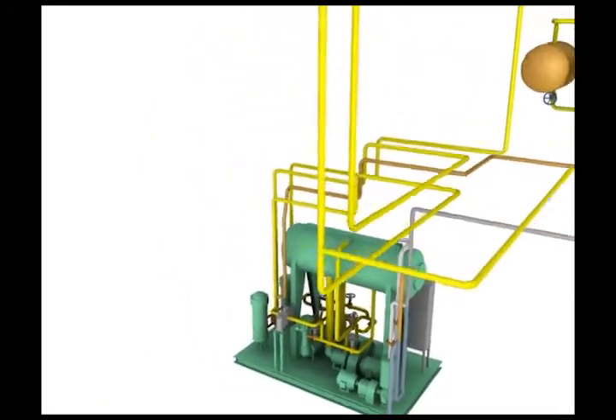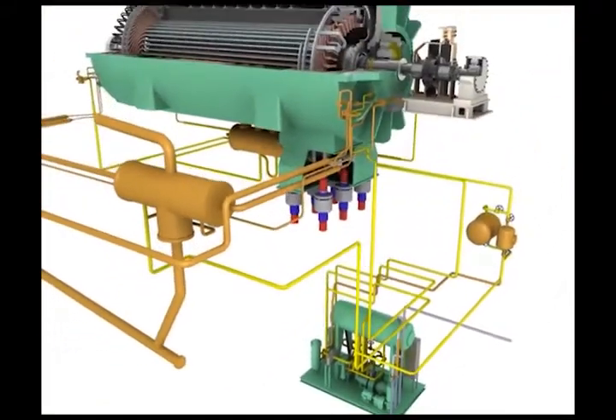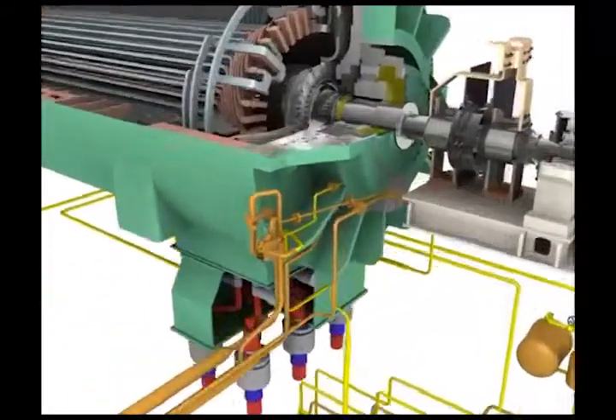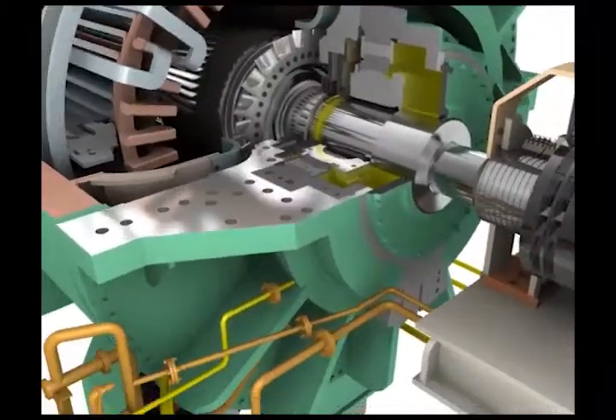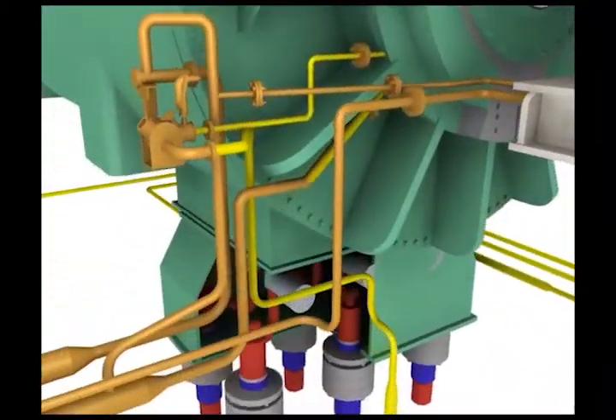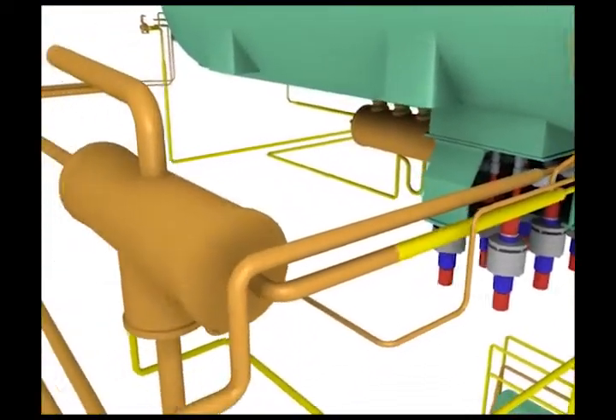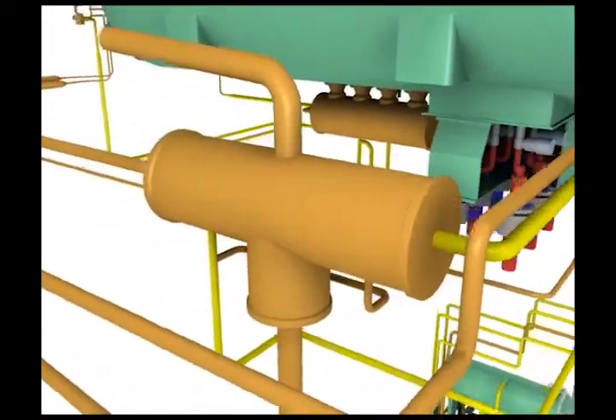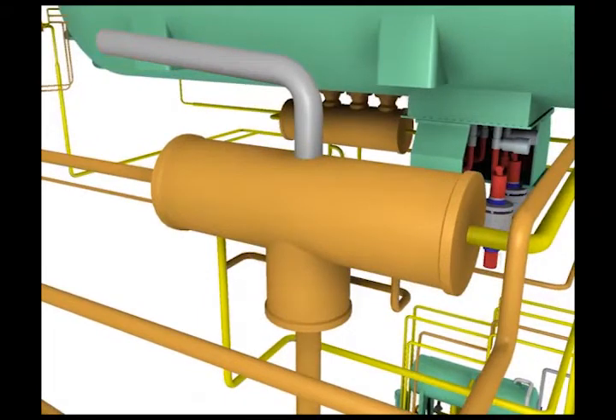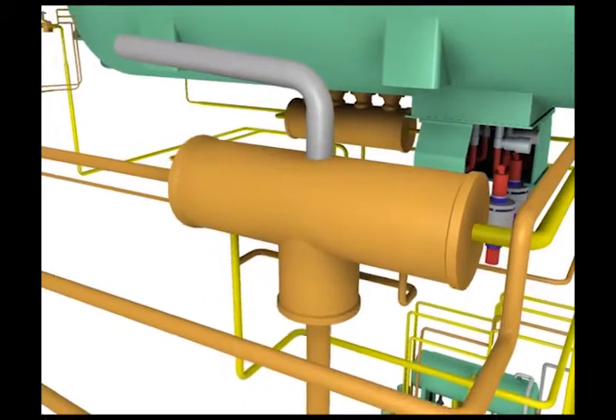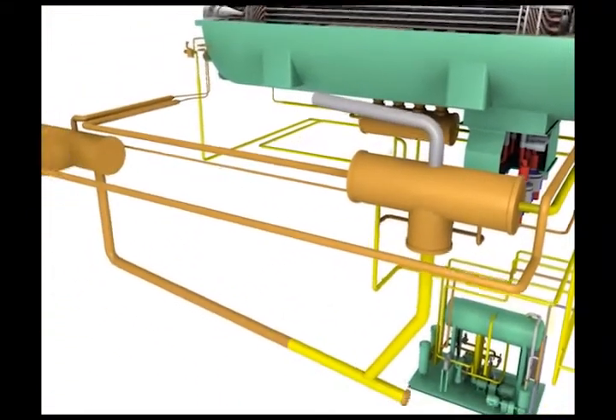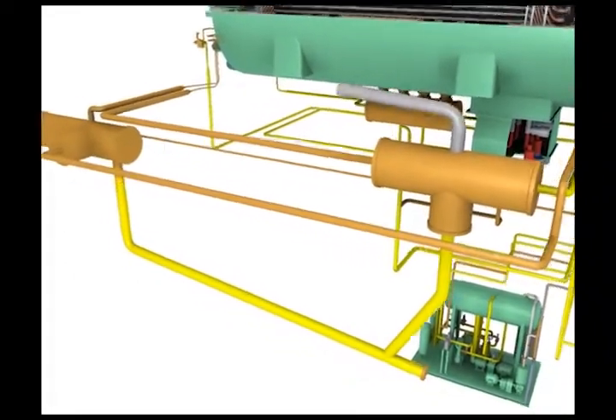The oil being drained from the generator's bearing oil and the shaft seal oil becomes common and goes into the auxiliary draining tank section. The air contained in the bearing oil and the H2 gas which has not been completely removed from the H2 draining tank becomes exhausted to the atmosphere through the vent from here and the oil circulates to the main oil tank.